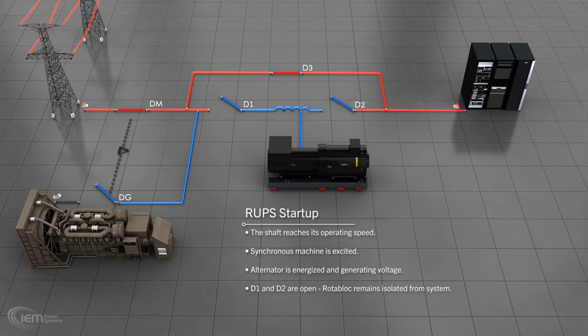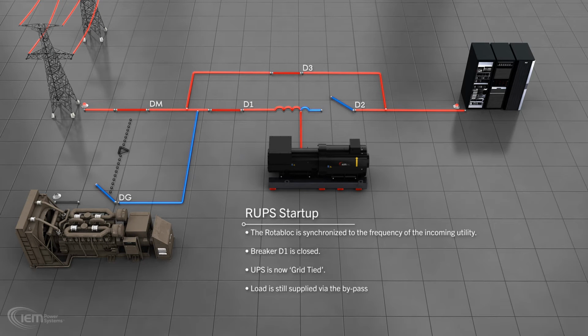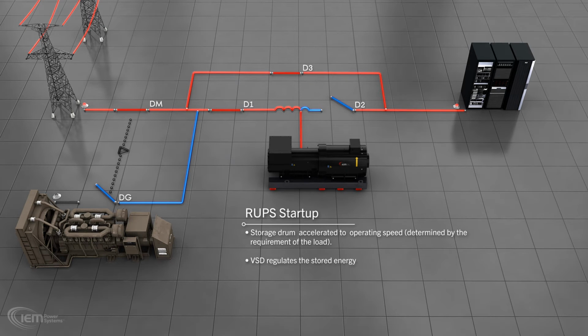When the shaft reaches its operating speed, the synchronous machine is excited and the alternator is energized and generating voltage. With D1 and D2 open, the Rotabloc remains isolated from the facility's power system. The Rotabloc is then synchronized to the frequency of the incoming utility, and breaker D1 is closed. The UPS is now grid-tied, but the load is still supplied via the bypass at this stage. The storage drum is now accelerated until it reaches its operating speed. This is determined by the requirement of the load that it will protect. The VSD regulates the stored energy by controlling the speed of the drum to match the requirements of the critical load. This unique approach further improves the efficiency and reliability of the Rotabloc UPS system.